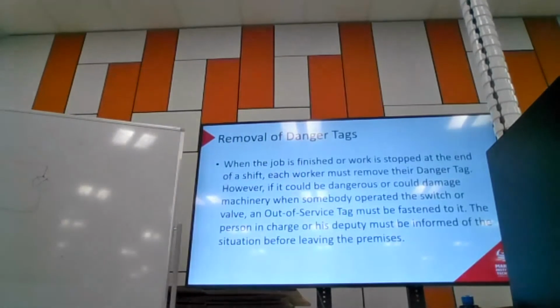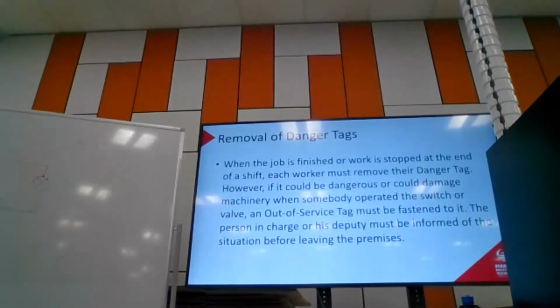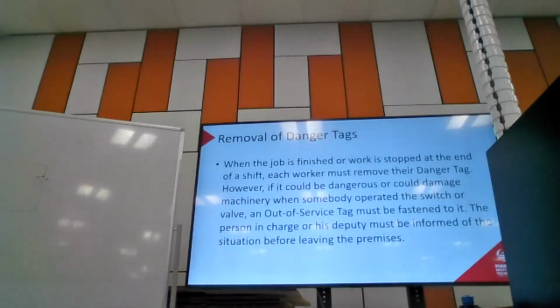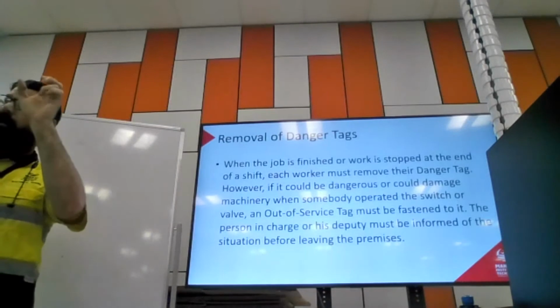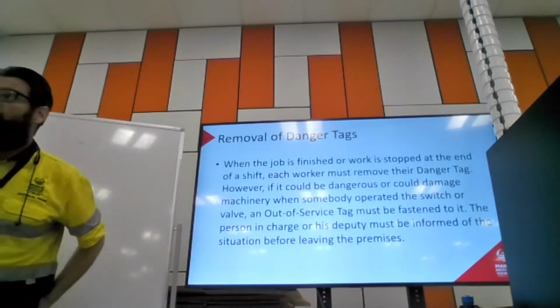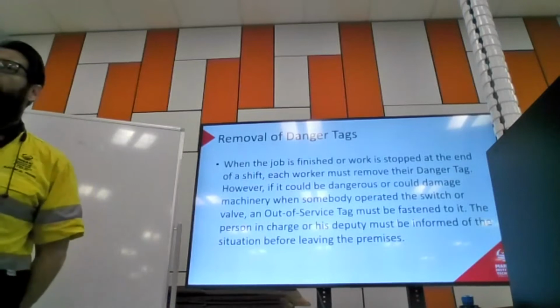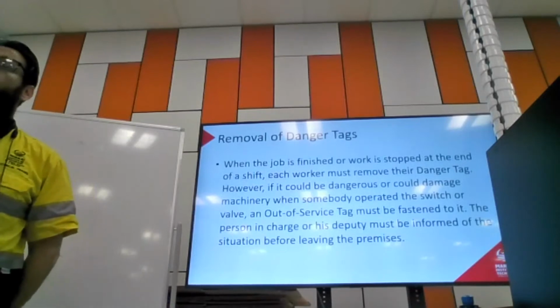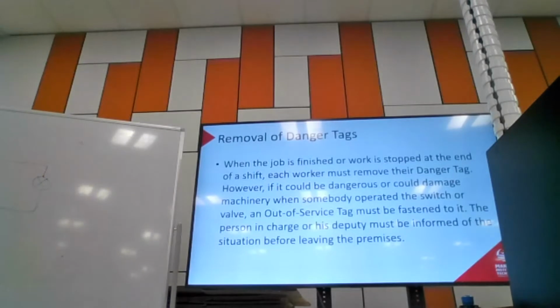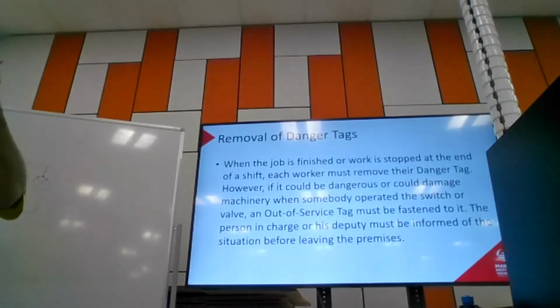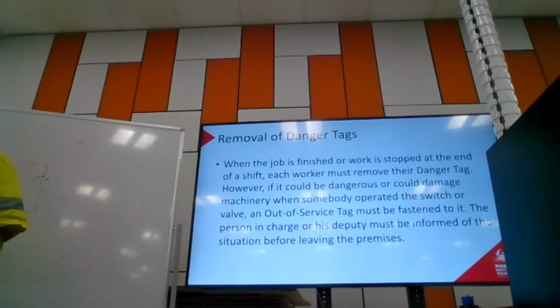Removal of danger tags. Who's going to remove a danger tag? Only the person who put it there. If we have multiple danger tags on the same switch, remember we might have one of those multi-clasps so a bunch of people can put locks on, who's going to remove them? Only your own one. Every individual who put one on must come and take it off. So we cannot turn that machine back on until every single person working on it has taken their tag off, which is their tacit approval that it can now be switched back on.